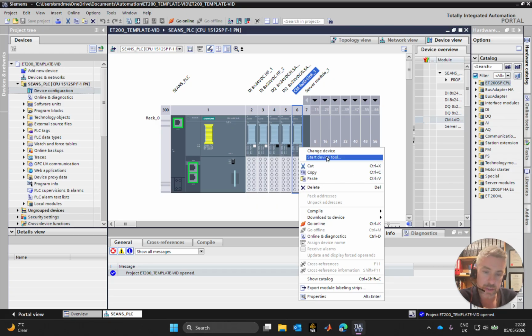Now the device tool here is black. Sometimes you might click this, or some people might right click this and they'll see that this is grayed out. If it's grayed out, do not worry, it's not the end of the world. It simply means that your S7 PCT, standing for port configuration tool, probably hasn't been installed, or hasn't been patched in at the time that your version of TIA had been installed in itself.